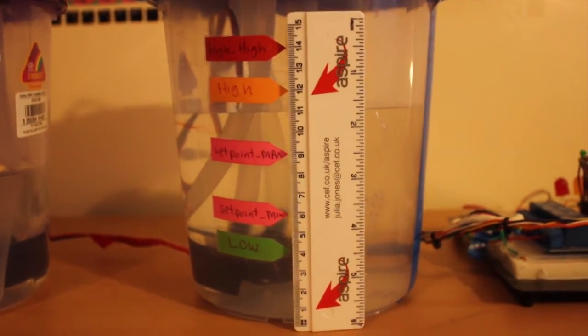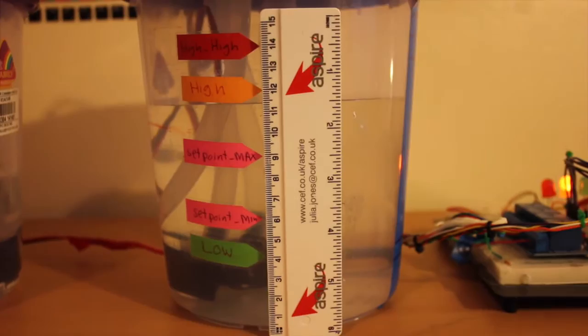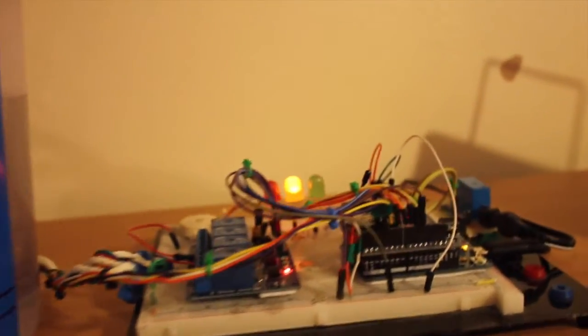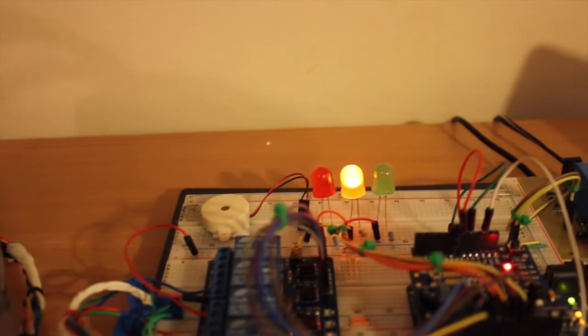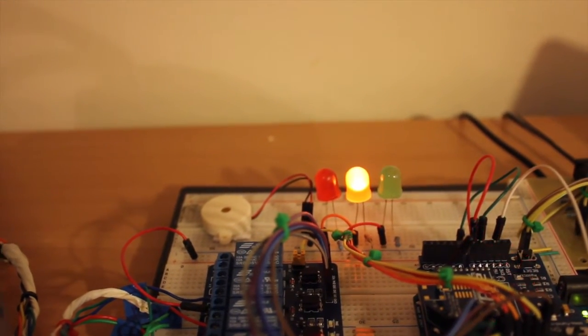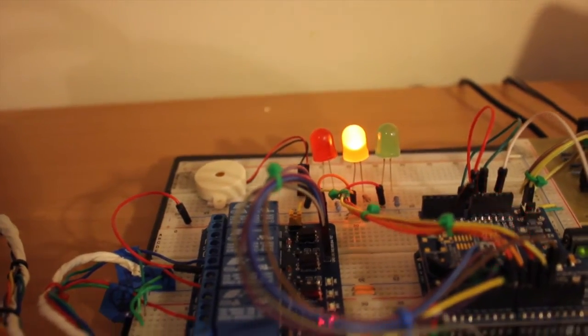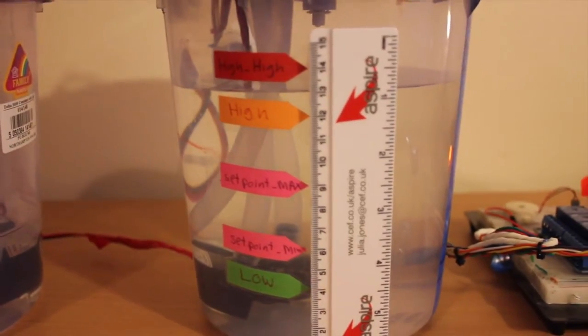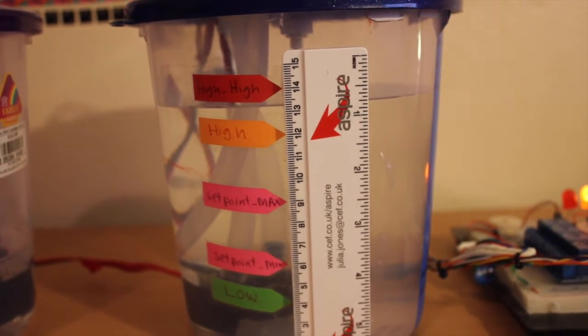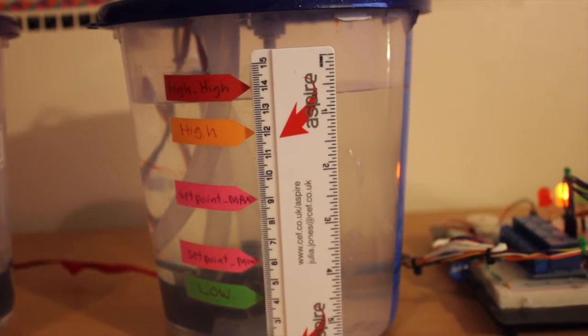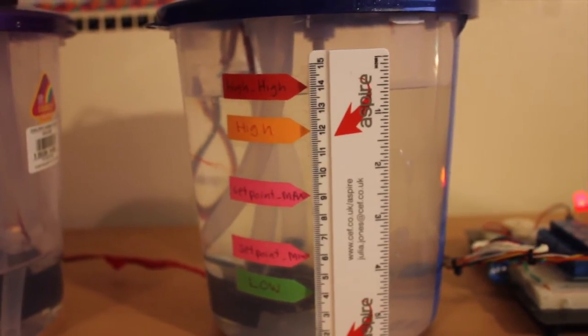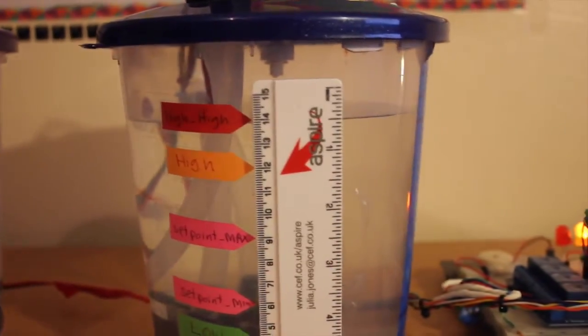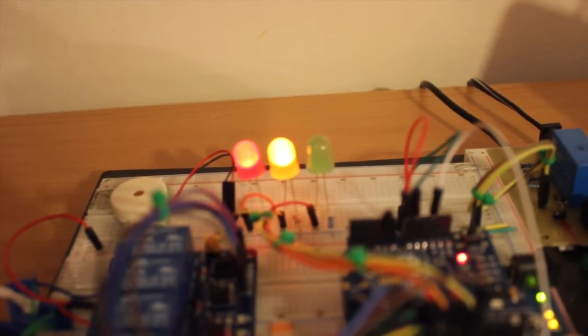as soon as the level reaches the high set point, it should trigger the high LED on, as we can see here, and the buzzer. And as soon as we reach the other high set point, it should trigger the other high LED and switch on the emergency outlet pump. So here, as we can see here, another LED is on, and the emergency outlet pump is on.